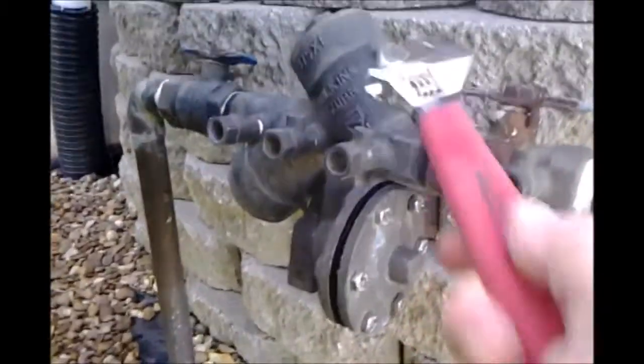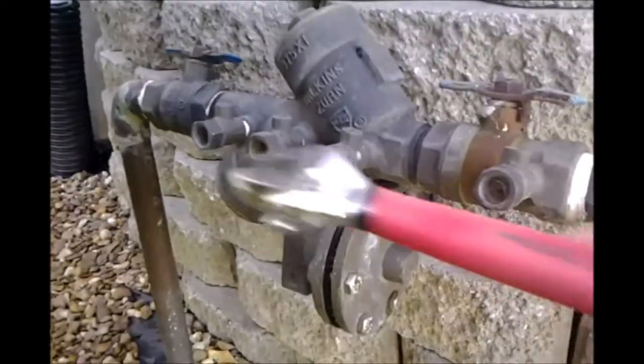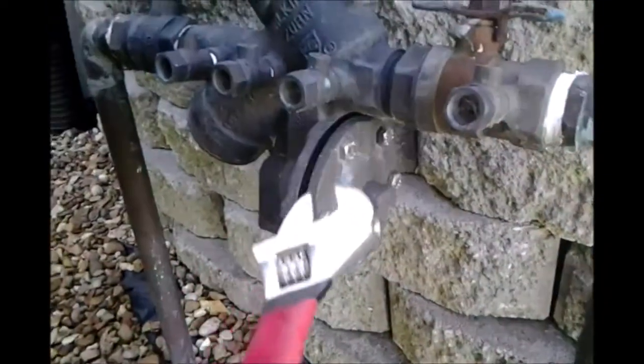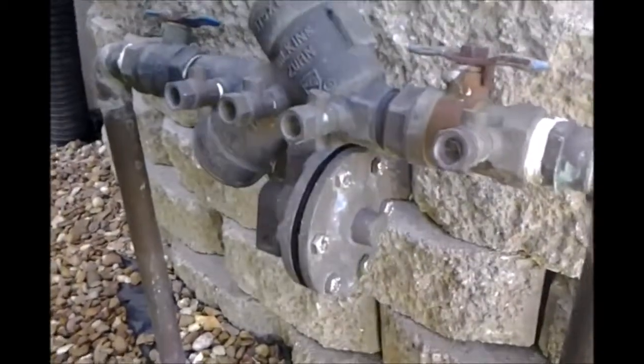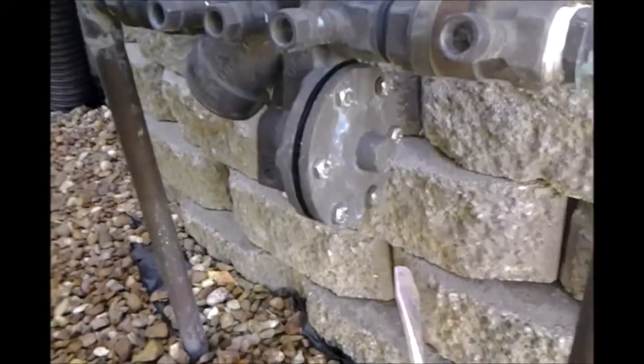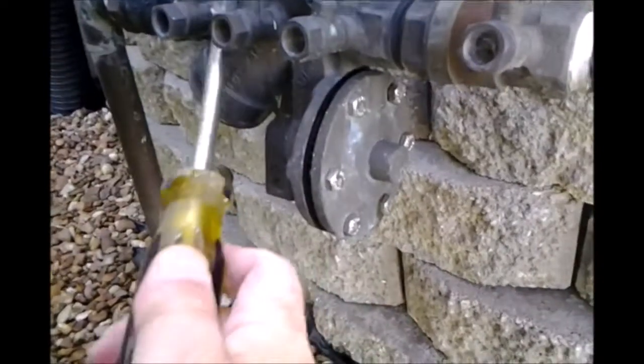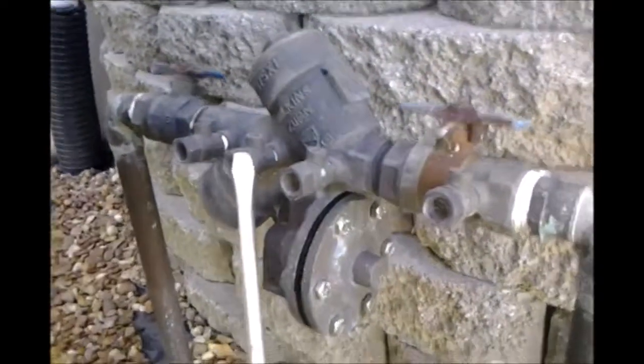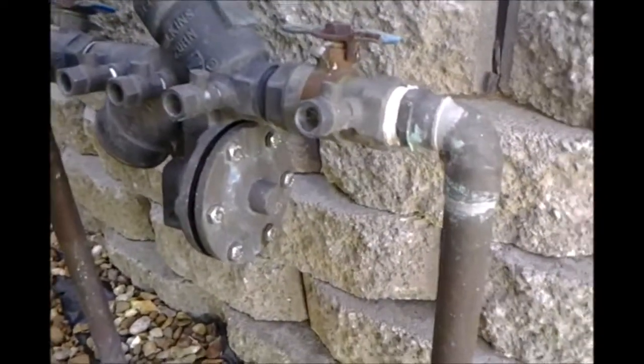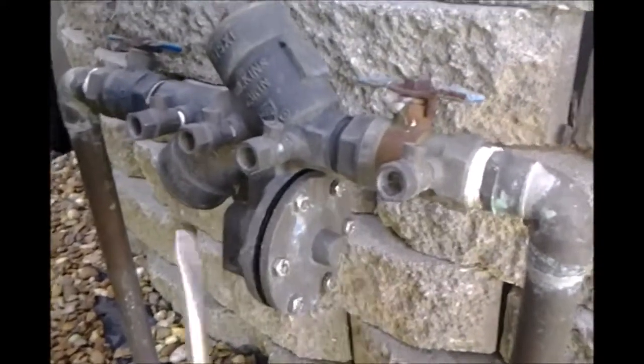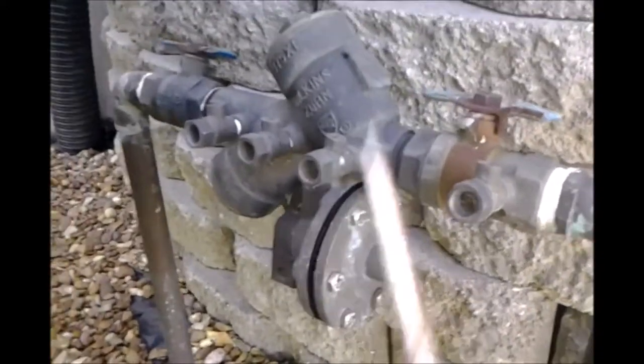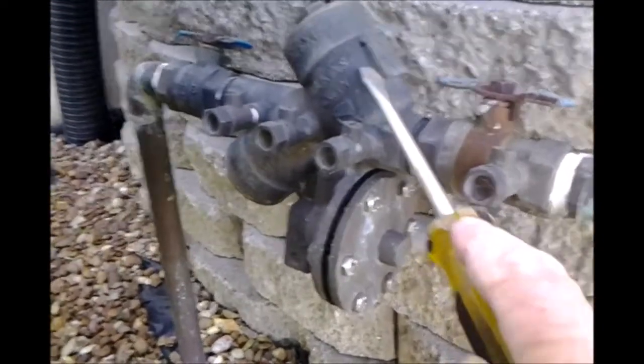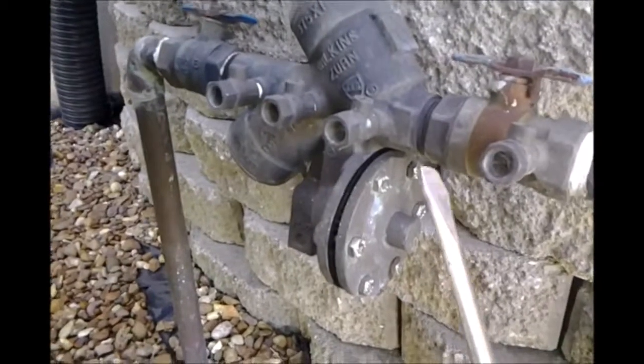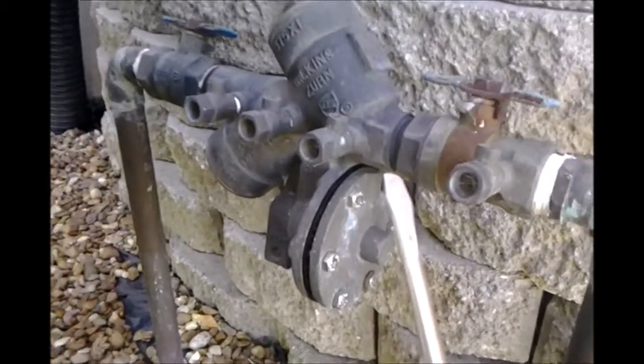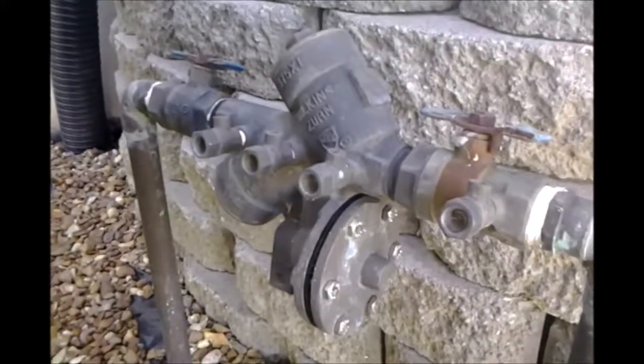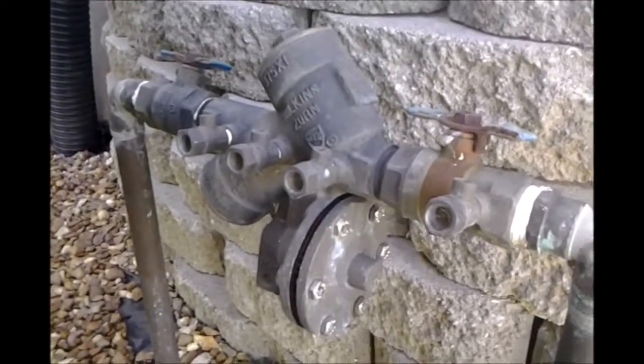This is where you test your check valve. This lets the flow go this way but not come back. And if your sprinkler system is on and under pressure, if there was a water main break out in the street and the water pressure went to zero or lower than what the pressure is here, theoretically, the water could flow back from your sprinkler system and into the city water main and contaminate it if you have dirt or whatever bacteria in your sprinkler system. So this valve keeps that from happening. This needs to be tested every so often to make sure it's working, and they hook up pressure gauges on both sides and pump it up to a certain pressure and see if it holds. So anyway, that's how to do the first step of your draining of your sprinkler system.